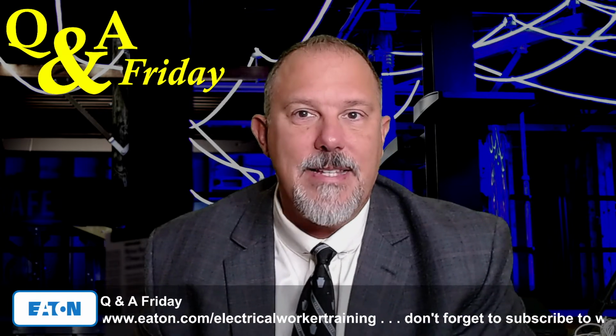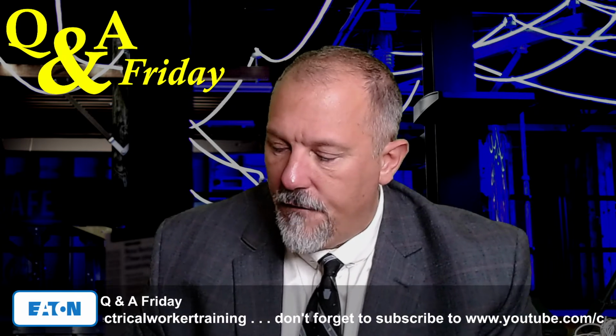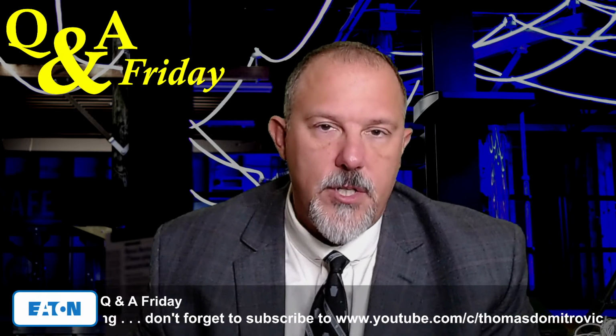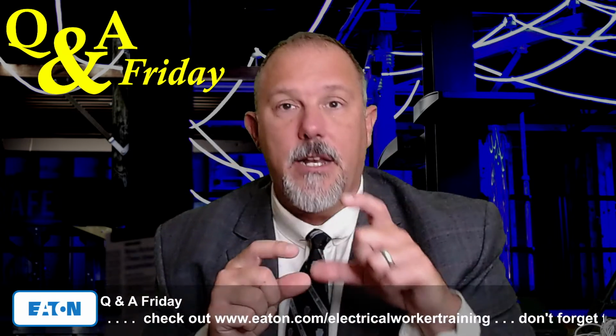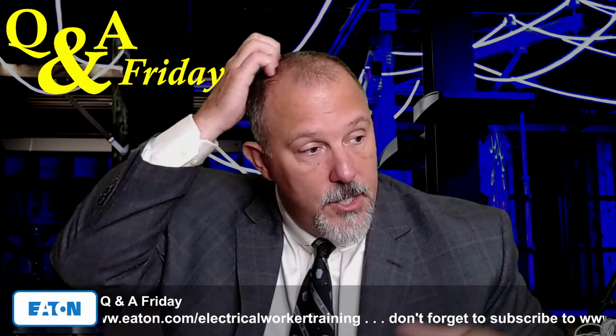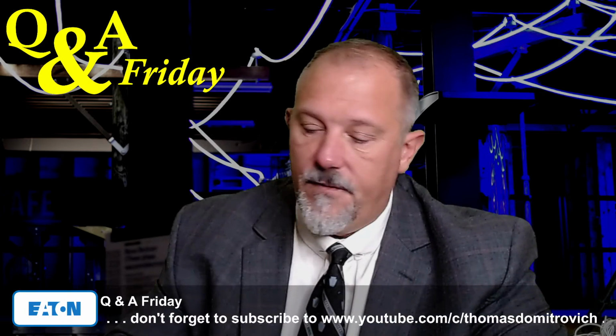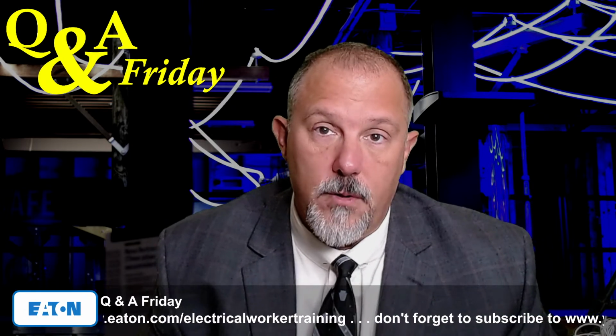The decimal points matter. So for example, the square root of 3 is 1.7321. If I take the 4160 and divide that by 1.7 and I don't use the 1.7321, then I'm introducing an error, and that's only one. That's a calculation within another calculation. So when you add these things up, it all matters. So what I did in this example was I calculated the secondary full load amps of, just for giggles, let's take a 1500 kVA transformer, 4160 to 480 volts, and let's calculate the secondary full load amps.